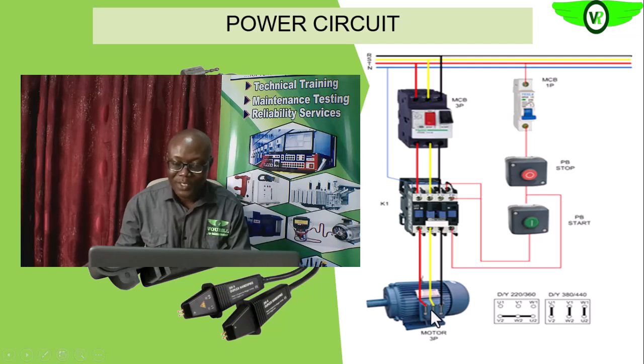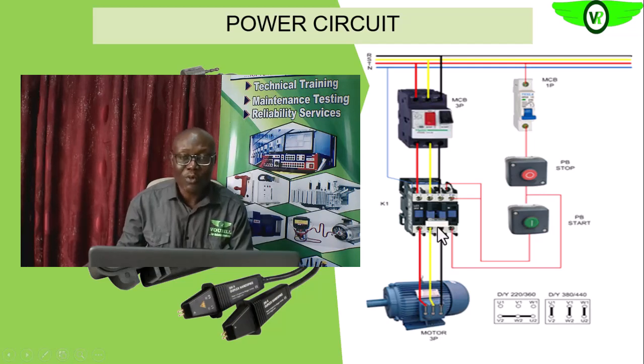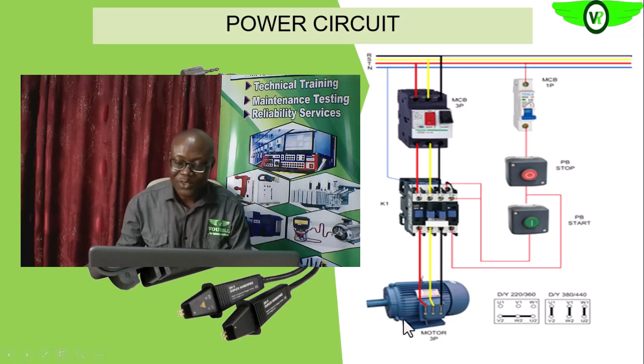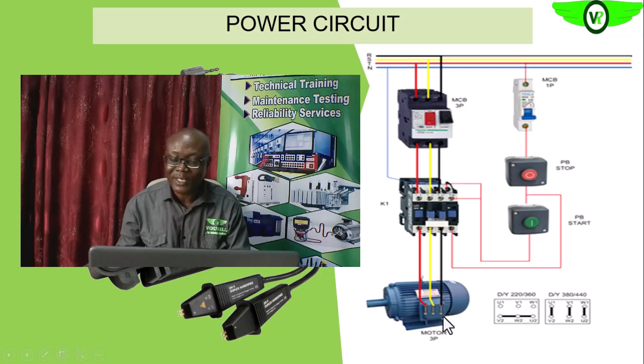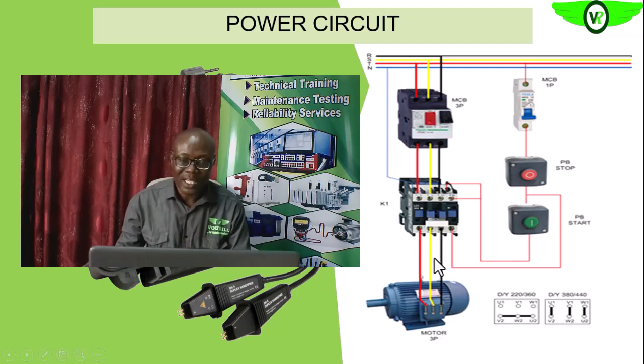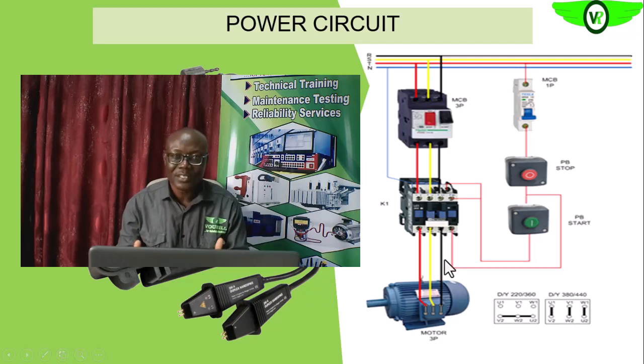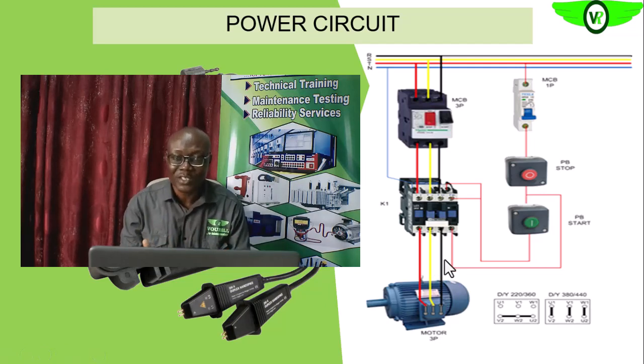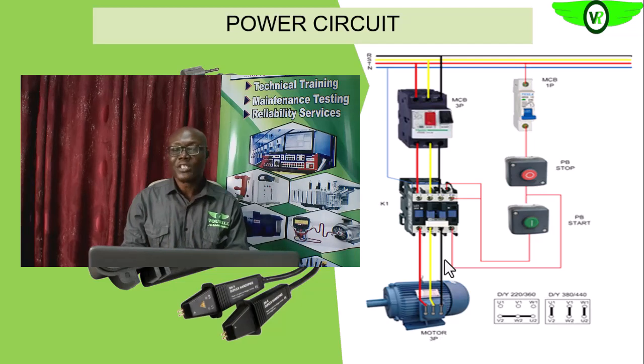Remember, we tested from here to, we started the test at the MCC. So what will happen is that you can disconnect, go to the motor in the feed, disconnect these 3 terminals, test the winding resistances. Okay, so if the winding, the resistance unbalance is not up to what you have, it means that the unbalance is generated along or is created along these lines. So it could be that we have joints on these cables that are already failing, that are not properly made. Okay, so those joints, we can go and refix those joints so that we can improve or reduce the resistances of those joints.